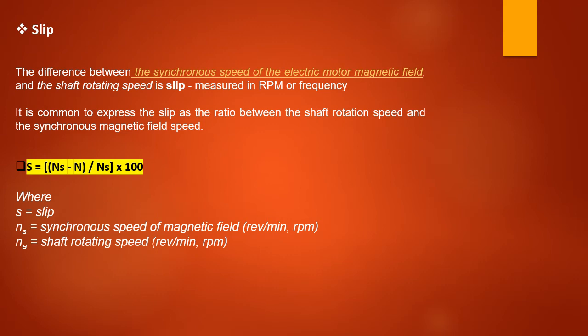Slip is the difference between the synchronous speed of the electric motor's magnetic field and the shaft rotating speed. It is measured in RPM or frequency and is commonly expressed as a ratio. The formula is: S = (Ns − N) / Ns × 100, where S is slip, Ns is the synchronous speed of the magnetic field, and N is the shaft rotating speed. Please remember this definition and formula and know how to apply it.